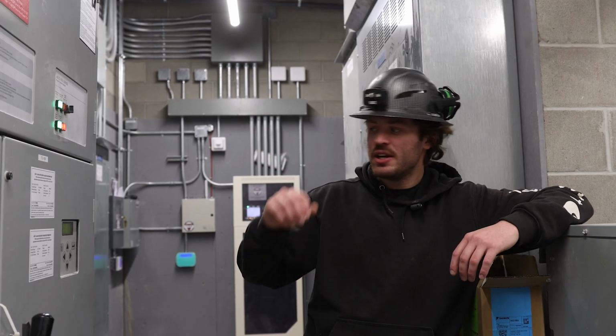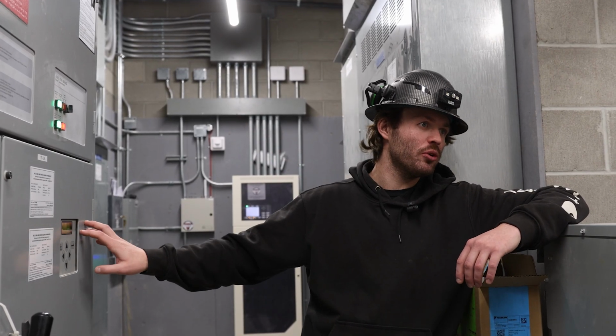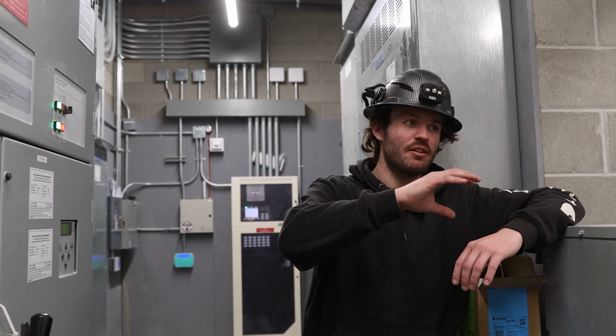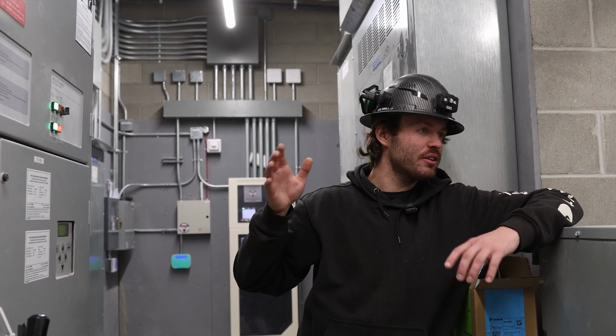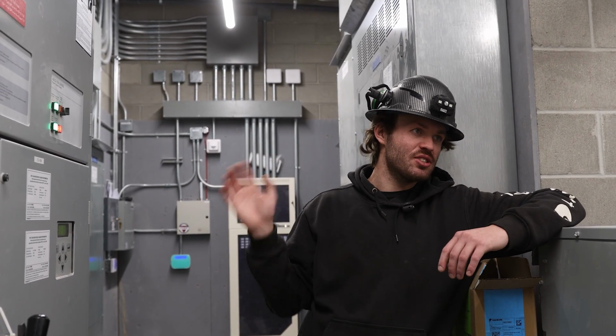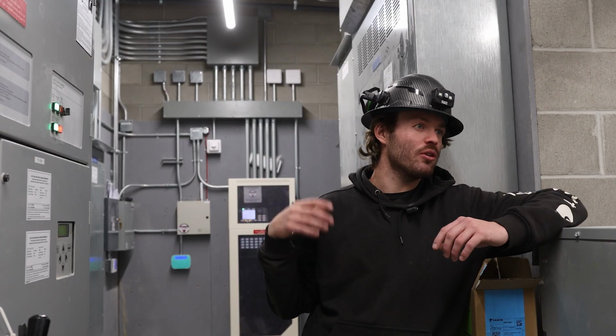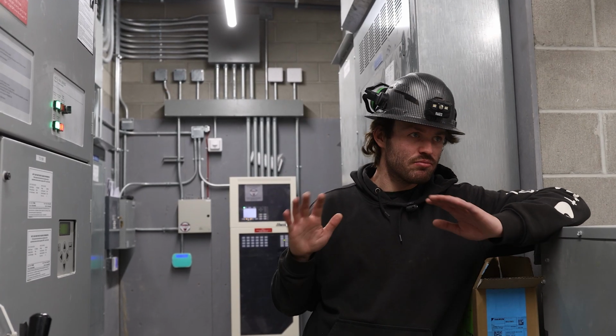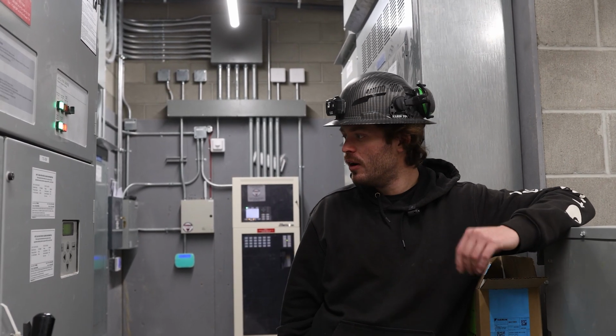After it does its transfer back, the generator will run a 5-minute cool down. So it's just running by itself. It's not powering the building. Running a cool down, letting oil and coolant cycle through it, just letting it go to bed cool. After that, it's going to automatically shut itself down.